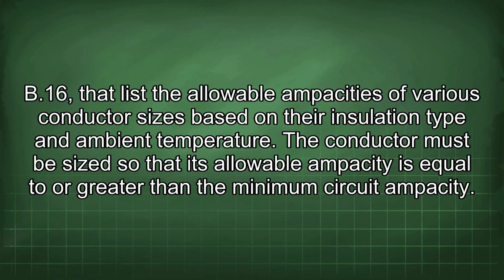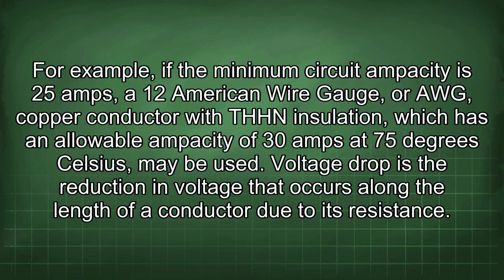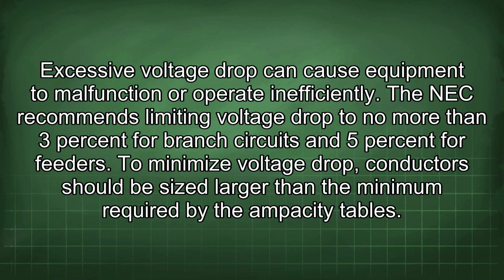The conductor must be sized so that its allowable ampacity is equal to or greater than the minimum circuit ampacity. For example, if the minimum circuit ampacity is 25 amps, a 12 American wire gauge, or AWG, copper conductor with THHN insulation, which has an allowable ampacity of 30 amps at 75 degrees Celsius, may be used. Voltage drop is the reduction in voltage that occurs along the length of a conductor due to its resistance. Excessive voltage drop can cause equipment to malfunction or operate inefficiently.